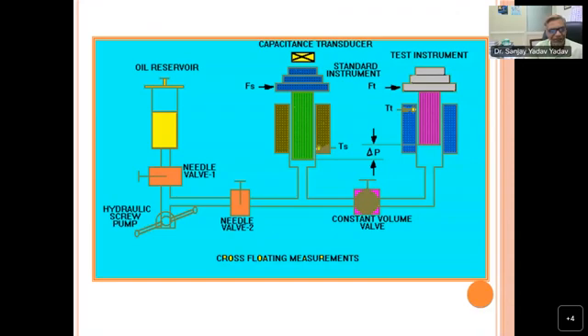Now we can go for the calibration of dead weight tester to dead weight tester. You have to install this equipment. In the middle you can see the standard dead weight tester, and on the right hand side you can see the test instrument or customer dead weight tester. When we are measuring, I said you have to consider the level difference. The level difference is determined from the bottom of the piston. Generally, this reference plane is marked on the dead weight testers, and in between we can use a constant volume valve.